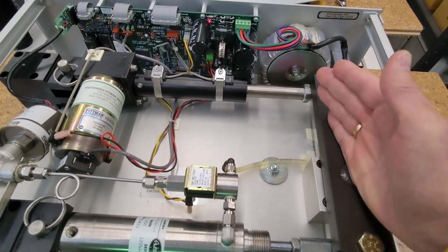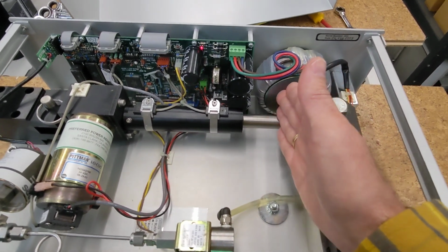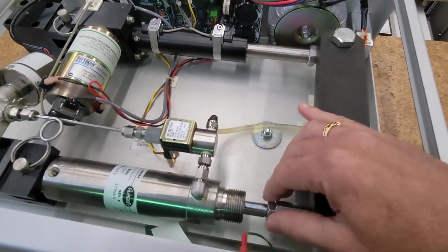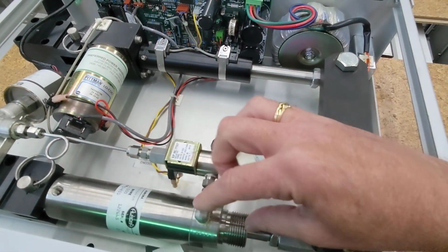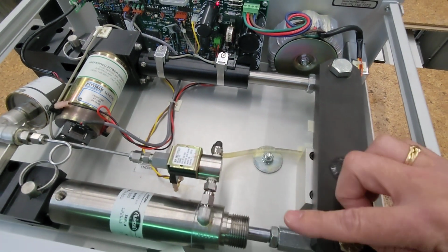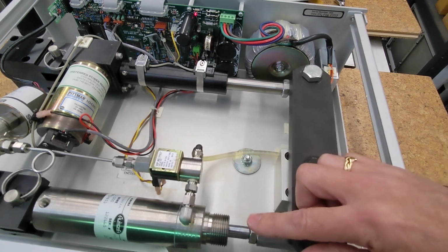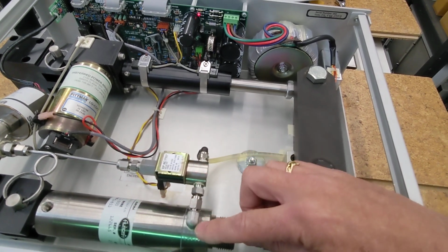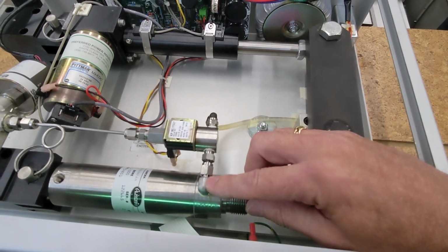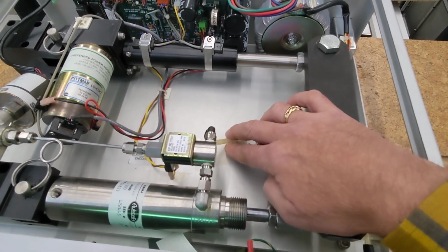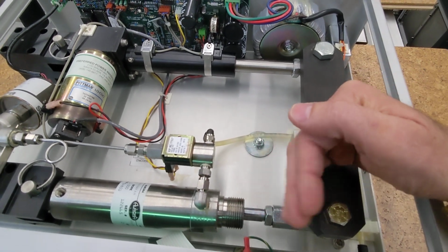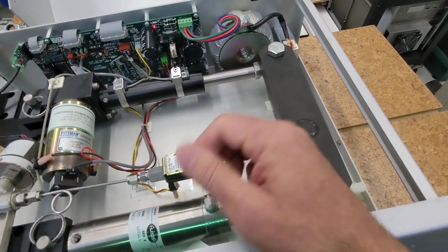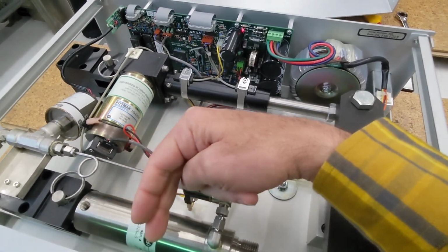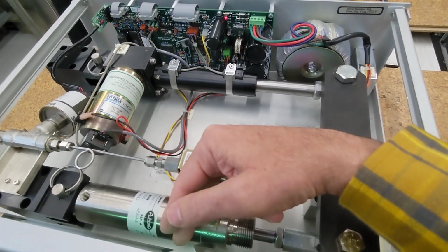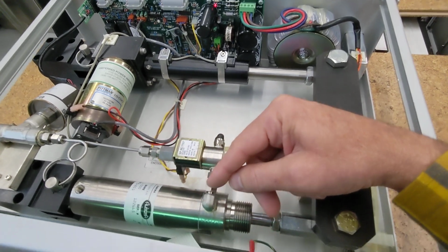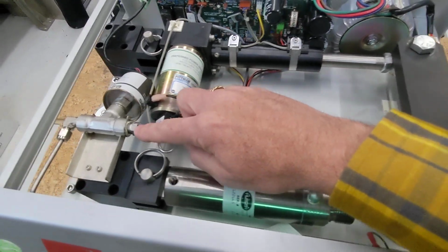So when this arm, when the actuator pulls in, it's going to pull out the cylinder and drive this back and dispense from here. When this extends, it's going to drive the cylinder in like this, which sucks in liquid from here. So on the suction side, we draw in from this tube. And when we go this way, it dispenses. There's a piston in here that pulls forward, reducing the volume in the front half of this cylinder. Reducing the volume means we eject the liquid. This valve will switch, and it'll come out here.